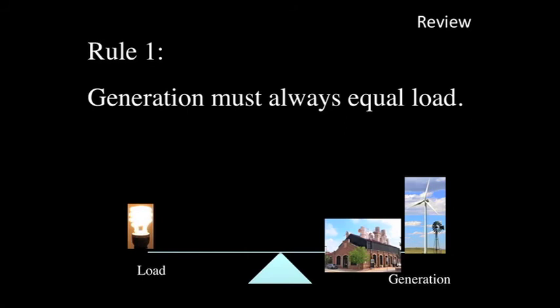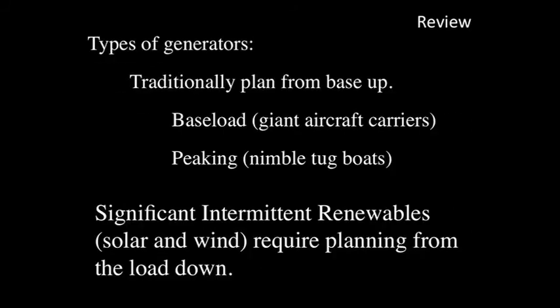So let's review. There's one rule: generation must always equal load. There are a number of different types of generators. Traditionally, we work from the base up with a baseload power plant and a peaking power plant. If you introduce lots of renewables into the system, you can't work from the base up — you have to work from the load down, taking away the actual renewables generating at that point in time and making up the rest with nimble power plants like natural gas.